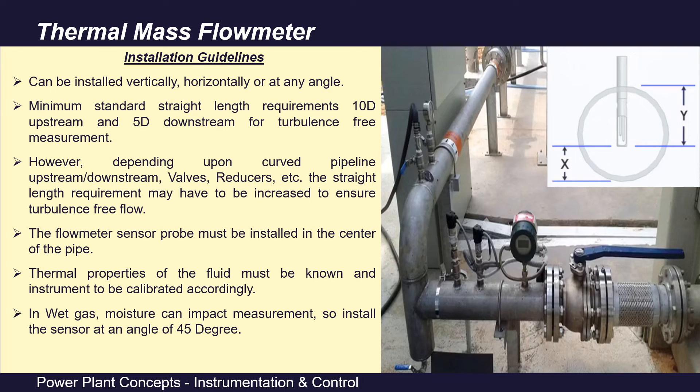That is 10 times the diameter of the pipe upstream straight length requirement, and 5 times the diameter of the pipe downstream of the instrument is required. But suppose if we have a valve, reducer, expander, or bend, in that case we have to see the turbulence effect, and then we may have to increase the straight length requirement to even 20D. Means we have to see what kind of obstruction is there. Then according to that, we have to increase the straight length requirement to make this flow turbulence free.